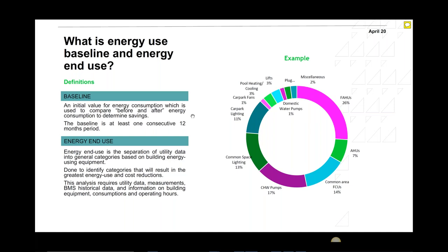Why is that? If you look at the end use analysis, you can see that there are no chillers. I can see chilled water pumps. So there are some pumps pumping chilled water within the building. So it cannot be not cooled because I have fan coils, I have air handling units. It's not going to be air cooled chillers because I don't see any chillers here on the end use analysis. So the only answer could be district cooling.